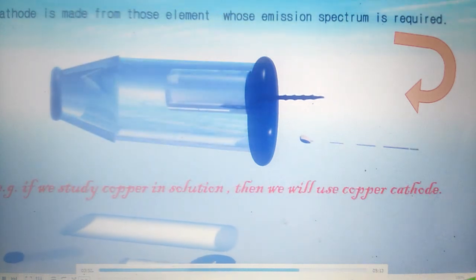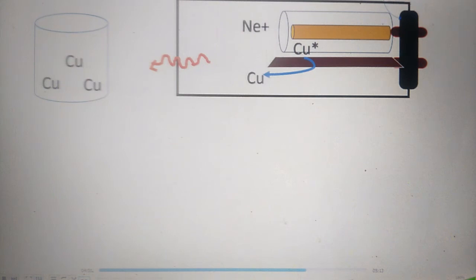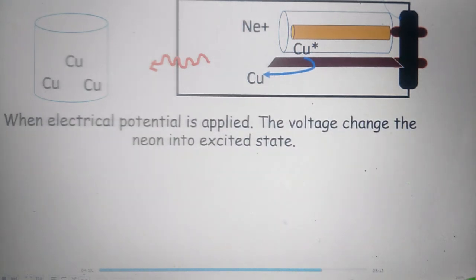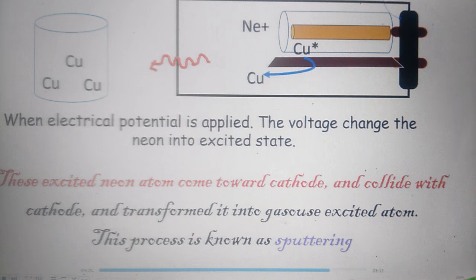If we study copper in solution, then we will use a copper cathode. Working principle: when electrical potential is applied, the voltage excites the neon into an excited state. These excited neon atoms move toward the cathode, collide with it, and transform it into gaseous excited atoms — a process known as sputtering. In the excitation process, specific wavelengths are emitted which are used in the analysis.